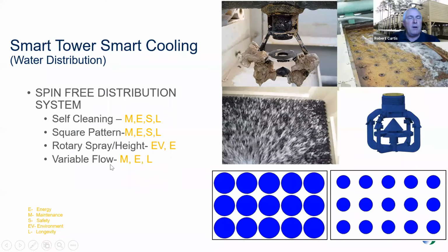Looking at the variable flow example here on the right, this shows a similar pattern when flow is reduced across a cooling tower, which typically creates more void areas, more wet and dry locations, and less efficiency. However, Tower Tech's design, with its tapered shaft and spinning disc, keeps water spread across 100% of the surface area even when reducing flow. This significantly impacts energy use and keeps the tower in optimum shape from a maintenance perspective.